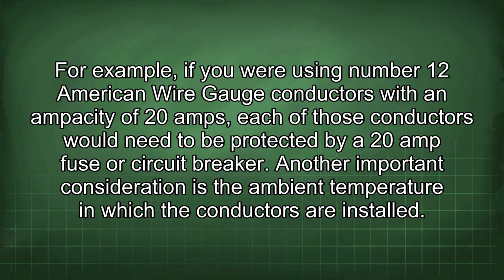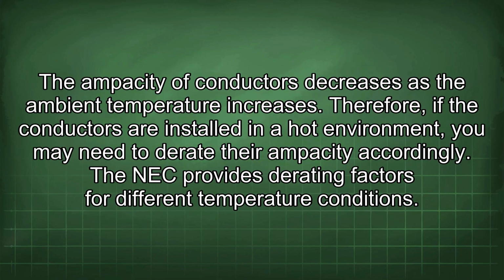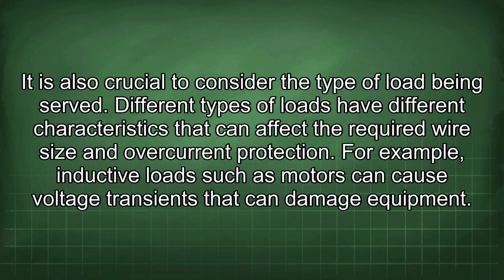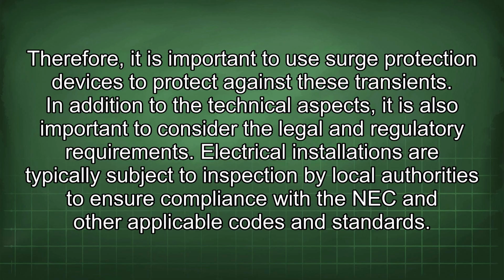Another important consideration is the ambient temperature in which the conductors are installed. The ampacity of conductors decreases as the ambient temperature increases. Therefore, if the conductors are installed in a hot environment, you may need to derate their ampacity accordingly. The NEC provides derating factors for different temperature conditions. It is also crucial to consider the type of load being served. Different types of loads have different characteristics that can affect the required wire size and overcurrent protection. For example, inductive loads such as motors can cause voltage transients that can damage equipment. Therefore, it is important to use surge protection devices to protect against these transients.